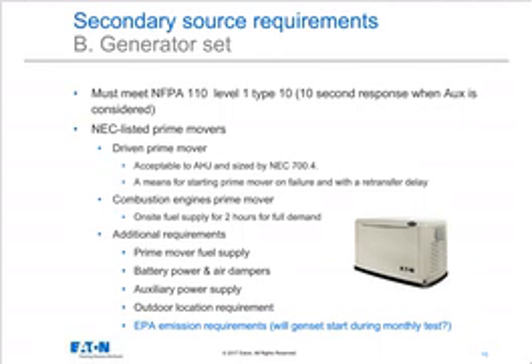And if I'm really going to meet that 10-second requirement, like I have to do in a hospital, for example, that's going to require a lot of technically unnecessary generator starts and stops. But that is the requirement. If the generator takes longer than 10 seconds or is delayed, say 30 seconds before it attempts to start, then a UPS is going to be needed to bridge the gap and make sure things like lights and other critical devices work during the time the generator takes to start.